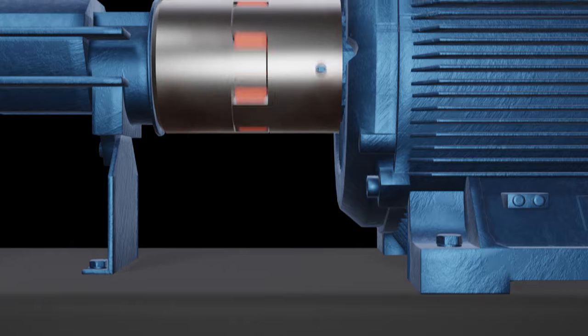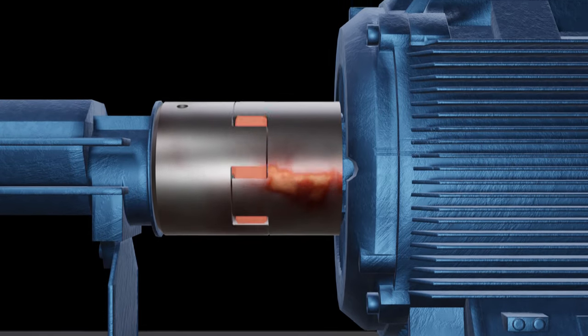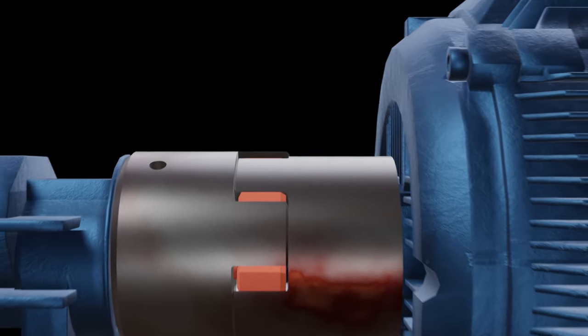Next, inspect the couplings. Oftentimes, you can determine if a coupling is misaligned by simply looking at it.